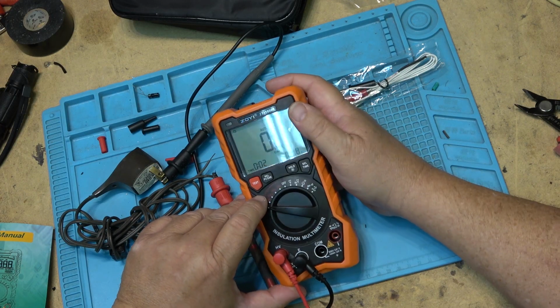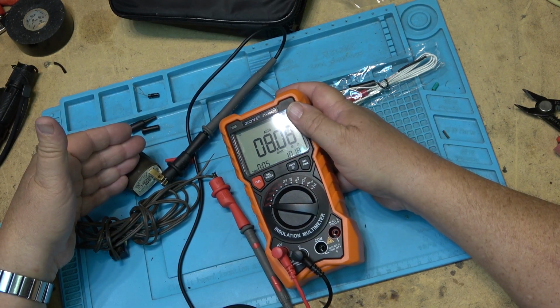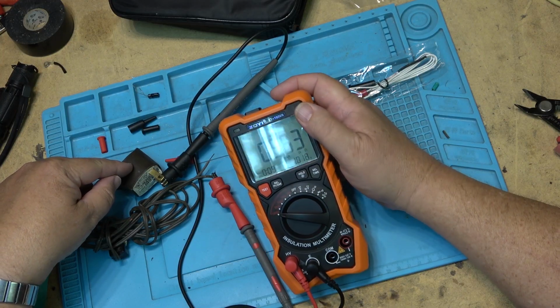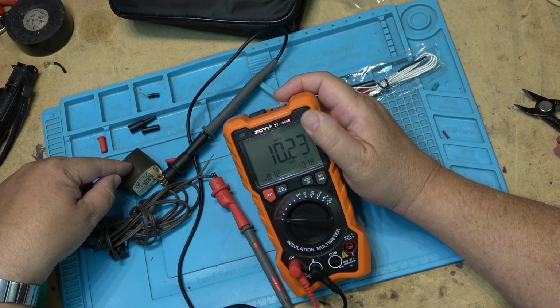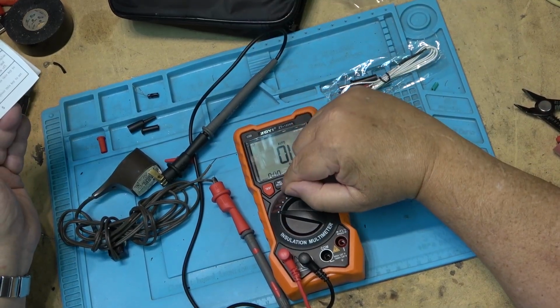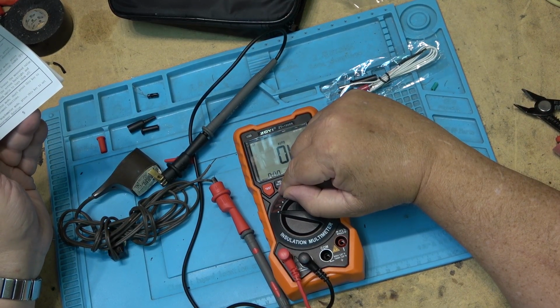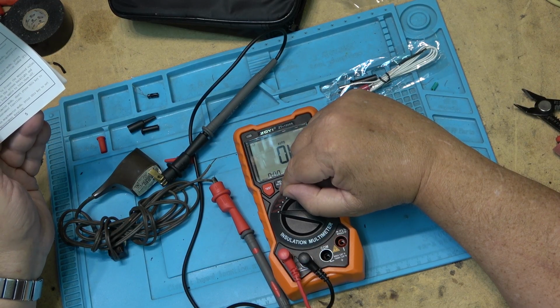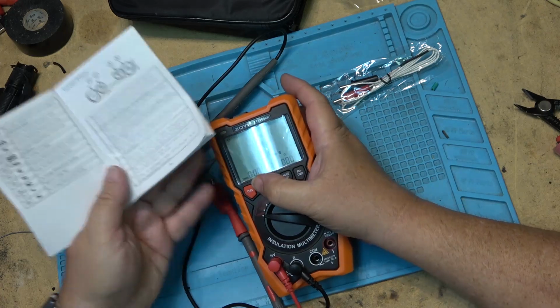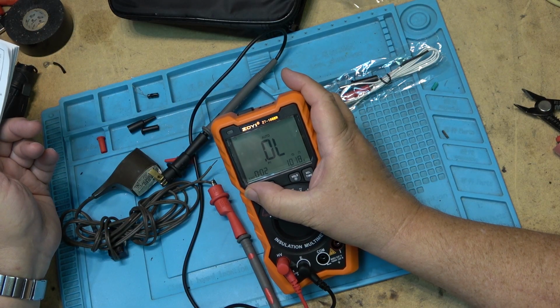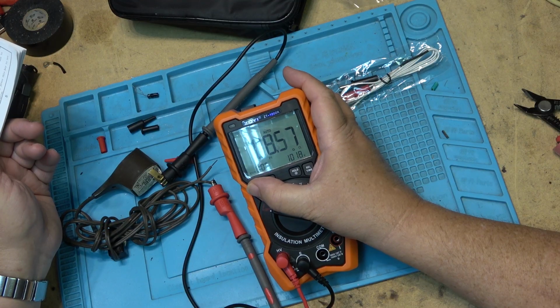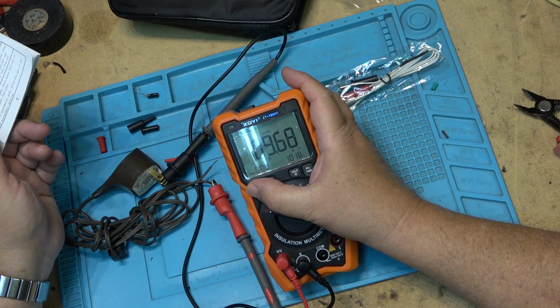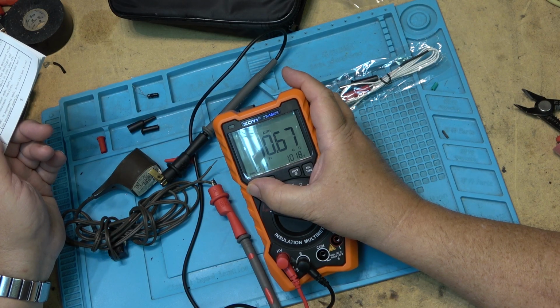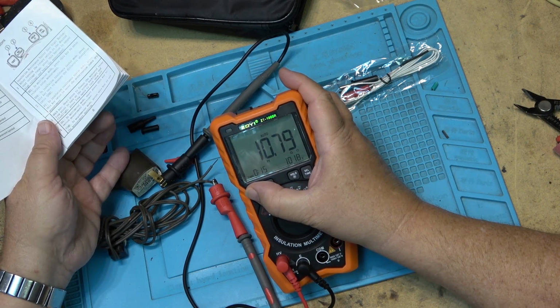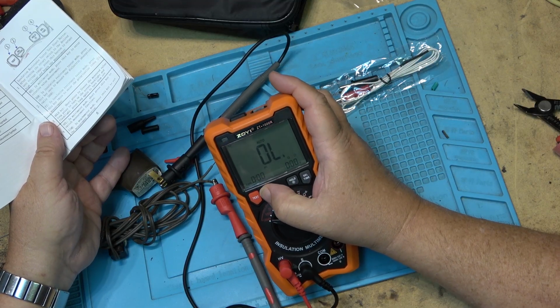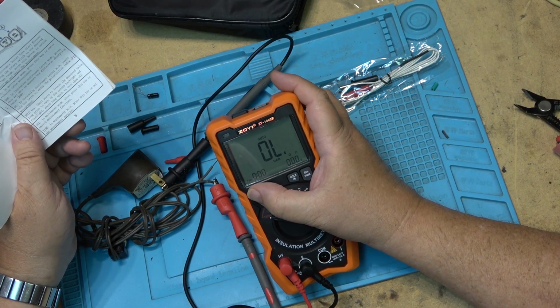Right now, of course, there's no breakdown on here because there are two separate windings and the isolation is good. The modes it will read in are relative mode, PI is polarization index, and DAR is your dielectric absorption ratio. So if we put it in PI and test it, it's going to give me a reading of 8.5, 8.9 going up at 1000 volts.